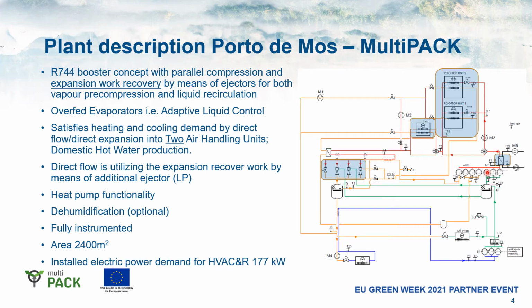The system also has a heat pump functionality, meaning that in the winter time, when the heat from the refrigeration part is not enough to heat the shop, an integrated gas cooler with an evaporation function for the heat pump mode is installed. So we can utilize heat from the ambient and lift it up to the desired temperature, which is required by the shop air handling unit. Further, we have the possibility to run dehumidification in the shop.